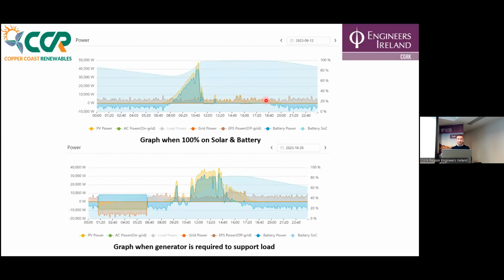And even in September, that solar was still running all the way up until 8 p.m. That's the difference on an east-west facing system. They don't have the massive peak during the day, so why install for that? Just because you can get extra kilowatt hours doesn't mean the client needs it. It's something everyone looking at solar, or designing new buildings, even if it's far lead or anything else, should remember - just getting the kilowatt hours doesn't mean it's actually going to do what the client needs. You should always be trying to match it to their on-site load.